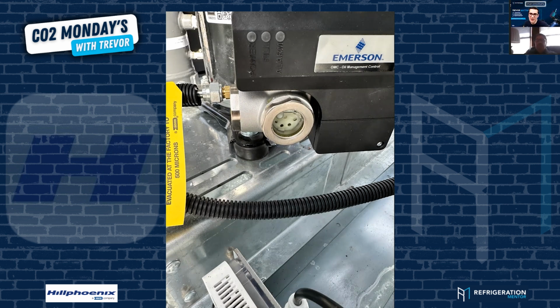Yeah, I have so many people in my training ask, well, what is the exact number that it needs to be? Well, it depends. It could be 70, it could be 120, but you need a differential. When you start getting below 60, you're going to start running into issues because it's just not enough to move that oil from your reservoir into your compressors, because that pressure could change a bit and then you might run into issues. So if you get 70, 80, 90, 100, depending on the system, it could be 120 PSI differential. So 5 or 6 bar, but there needs to be a differential. Your flash tank or your receiver cannot run at the same pressure as your medium temp suction. No different in your oil. Your oil needs to move.